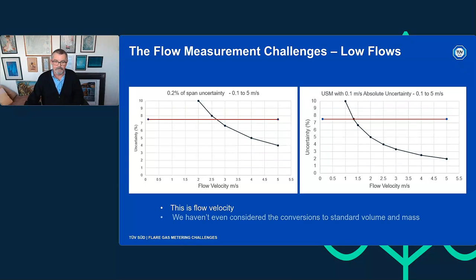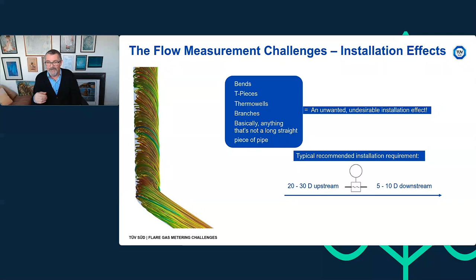We also have installation effects. If I look at a typical flare gas system, the inlet pipework has bends, T-pieces, thermowells sticking into the line, branches. And from a flow metrology perspective, anything that's not a long, straight piece of pipe is basically an unwanted, undesirable installation effect. Now, typically, the manufacturers will recommend 20 to 30D upstream, but they'll always quite rightly say the more, the better. And they usually recommend something like 5 to 10D downstream, again, quite rightly, because they're knowledgeable people. They'll say the more straight pipe you have, the better.